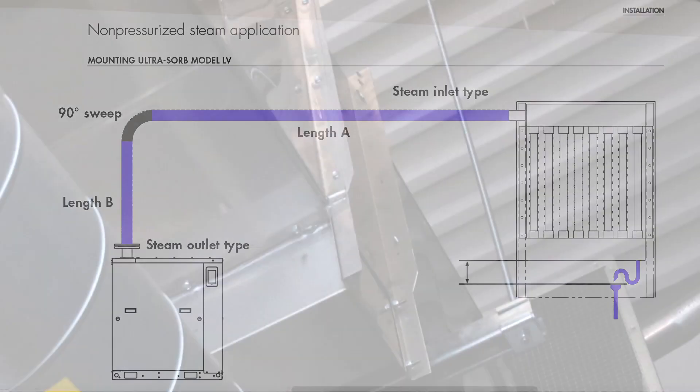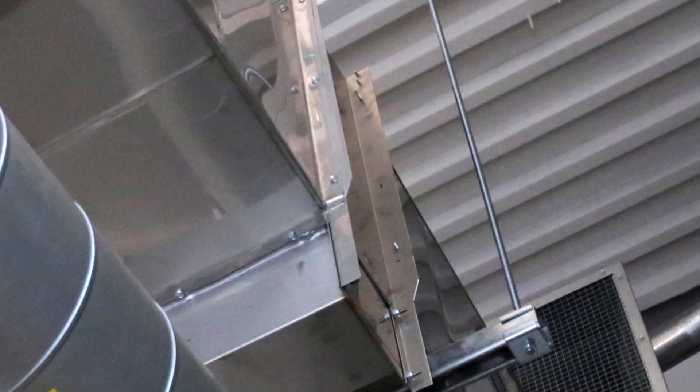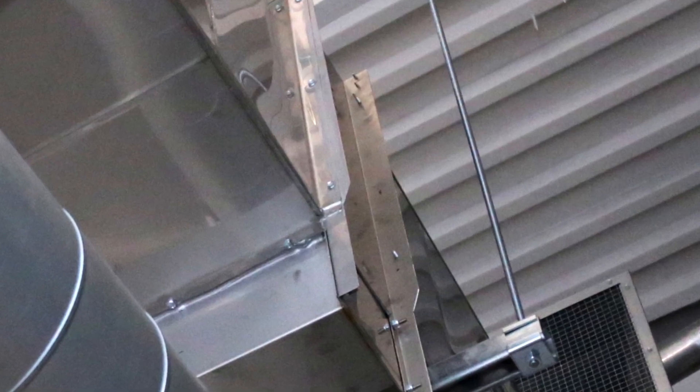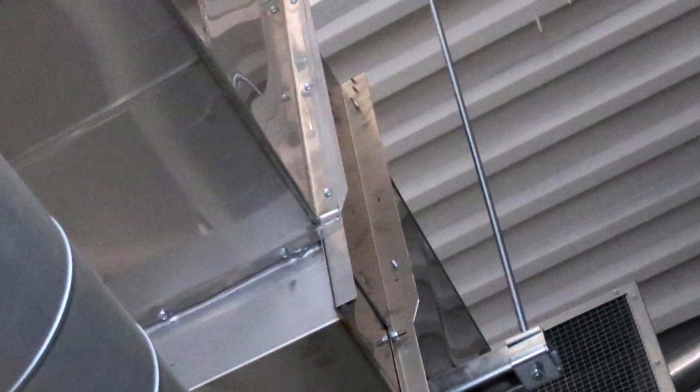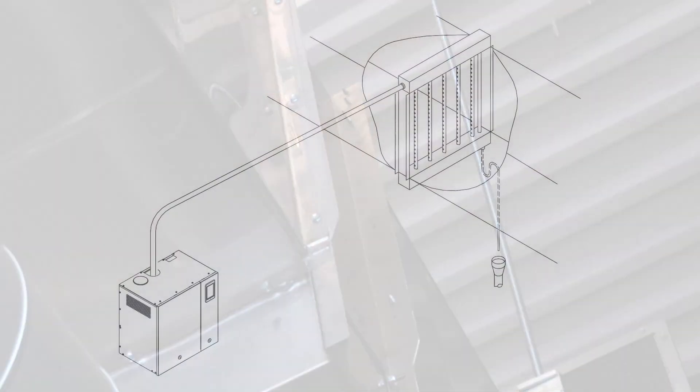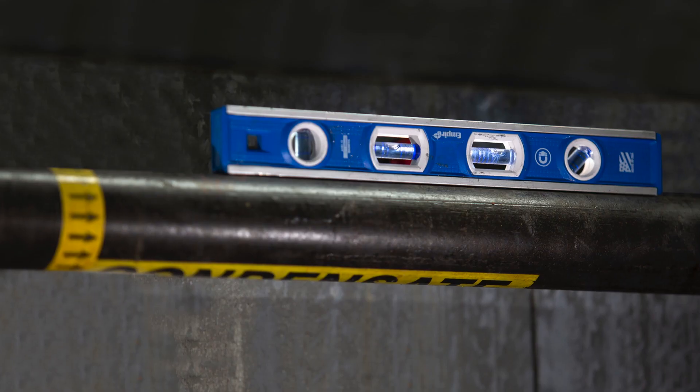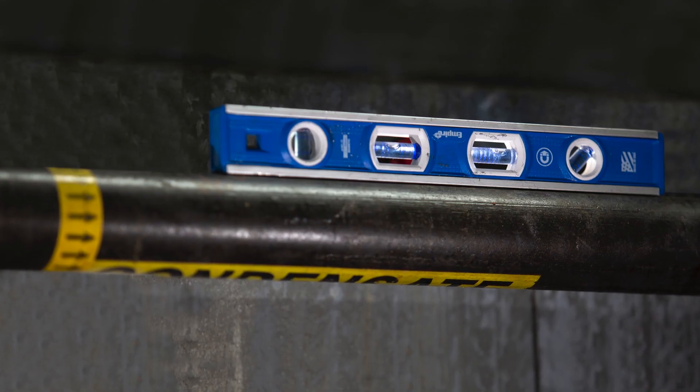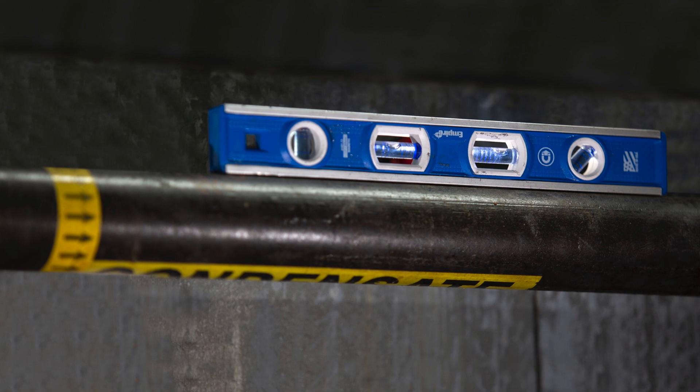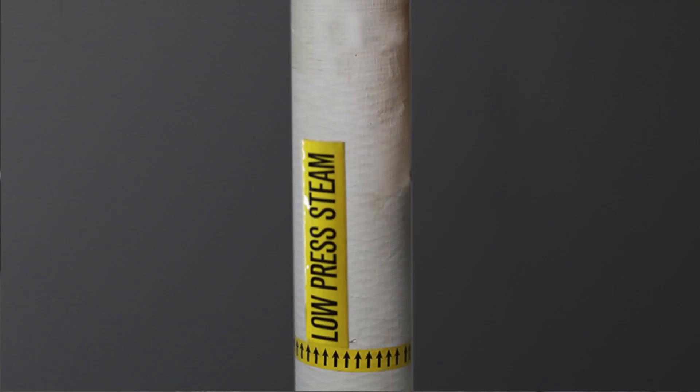Lift the dispersion panel into the duct cutout or the air handler and fasten it in place through the mounting flanges with a drill driver. Connect supply piping, connect condensate drain piping, check for leaks and proper pitch of piping, and apply insulation to piping.